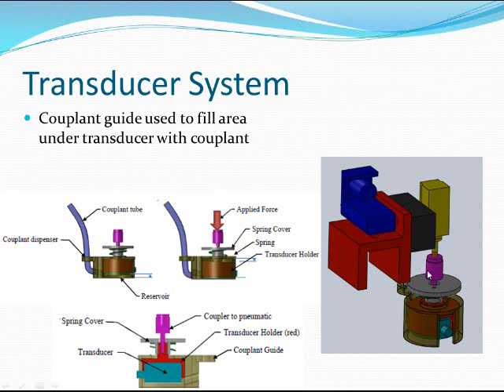A couple of pieces of equipment are necessary here: a linear actuator and a spring which allow this outer couplant guide to move upward once the transducer comes down. This specific gap area is where the couplant will be filled, and any excess couplant will be ejected out of this corner.